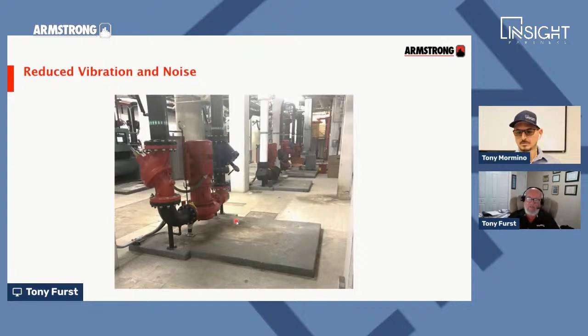The other thing to notice - there's no support underneath the pump. There are a couple of little supports underneath the pipe elbows, and the reason they're there is basically to keep the pump from acting like a swing. Those are not there to support any of the weight - all the weight is carried from the pipe hangers up above. Those stands are there to keep the pipe from swinging, that's all they're there for. Not for the weight of the pump.